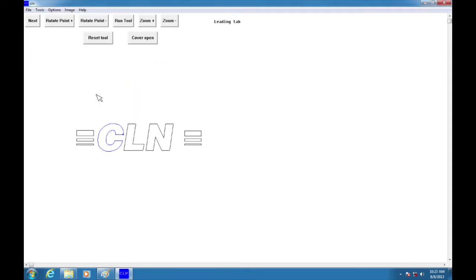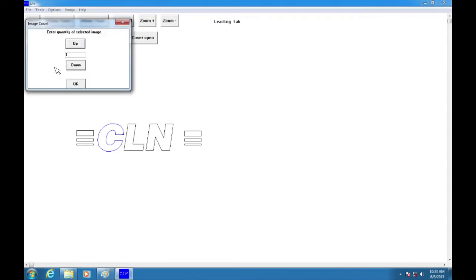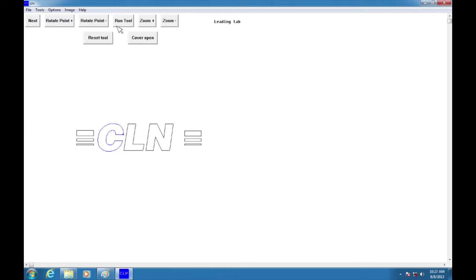Now there's 3 ways to process the letters. The first way is select the letter and click Reset Tool, which will bring the cover down. Then press Run Tool. The second way to process a letter is go to Options, Repeat Image Count, and here you can select up or down and select how many times you want to run that one letter. Click OK, then click Run Tool.